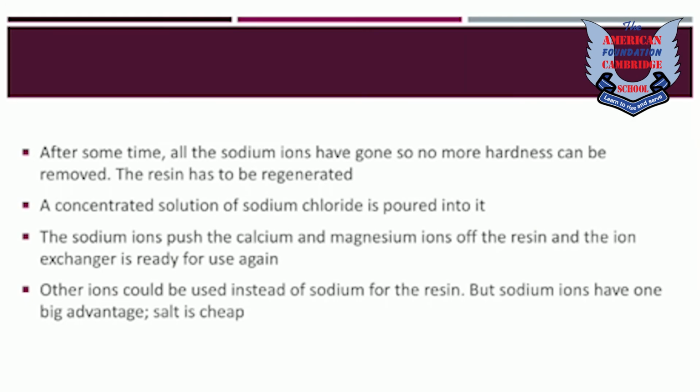After some time, all the sodium ions have gone, so no more hardness can be removed. The resin has to be regenerated. So if we perform this process again and again, then a time will come that the ion exchange resin will no longer be utilized, because it will be spoiled by continuous absorption of calcium and magnesium ions, and in this way we have to replace it or we have to regenerate it.